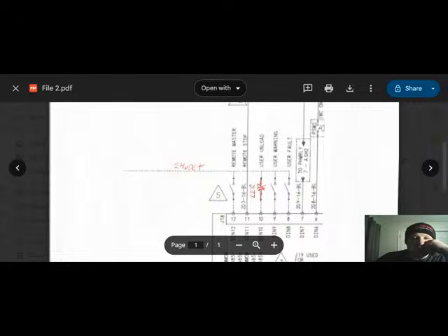When that happens, that manual unload signal goes away and the compressor will run as normal. When the lights go off and the relay coil is de-energized, these contacts will close and this user unload signal can come in here and unload the air compressor. It'll run for its designated time, whatever that is, 10 minutes, 5 minutes, whatever, and then it will go into standby and wait for this signal to go away. So when you come in the morning, it puts the lights back on, it opens, and the compressor says, hey, it's time to get to work. So it loads and locks and rolls.